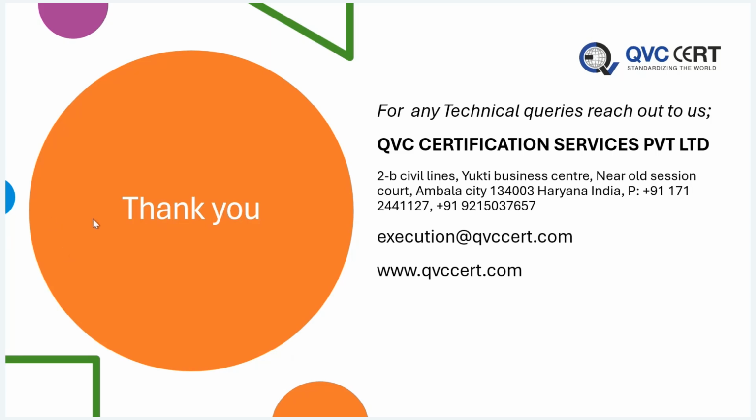Is a test license also needed for SAMD? As per the medical device rules, yes, you require a test license for SAMD to show how you validated and how you did your pre-commercialization activity.